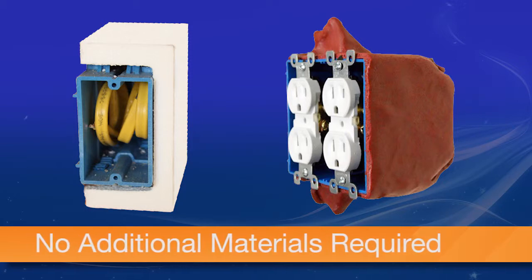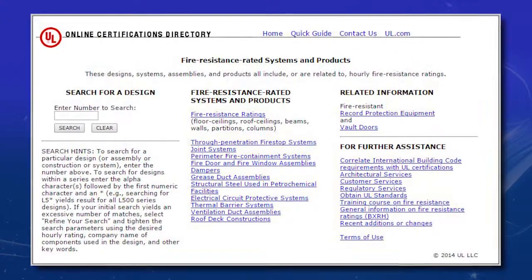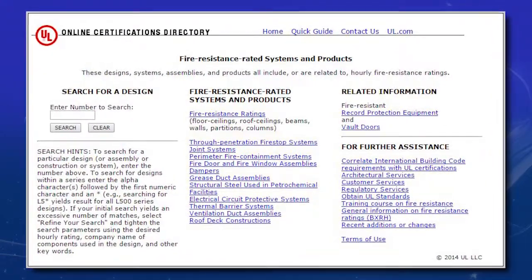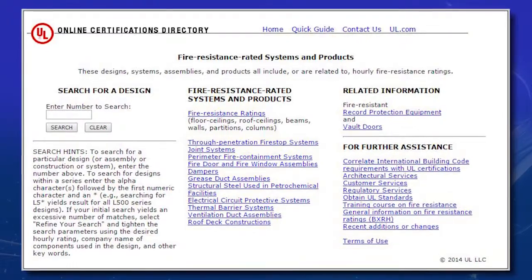Three-inch horizontal separation is approved in all U300 wall series configurations, meaning all wall designs found in the UL fire-resistive directory from U301 through U399 including those staggered stud designs and separated wall designs.